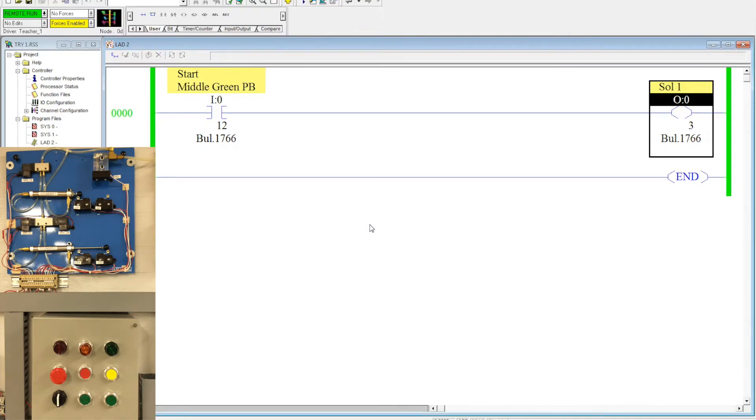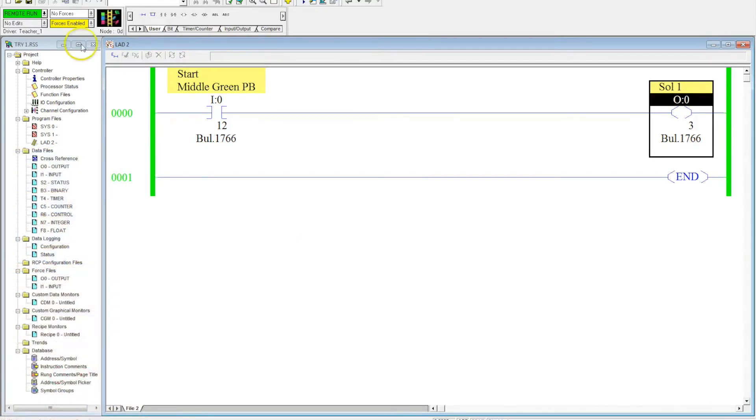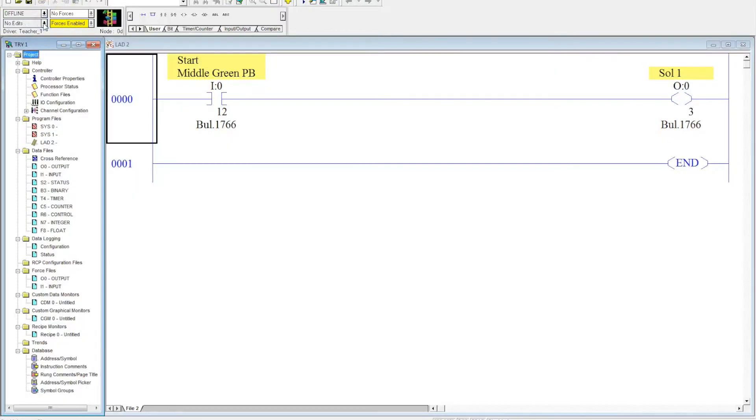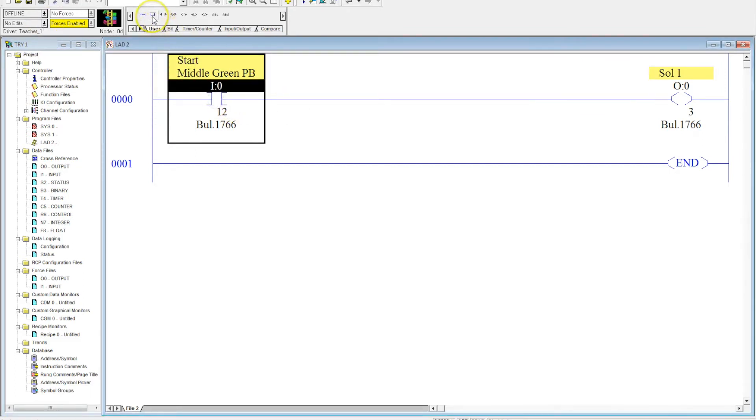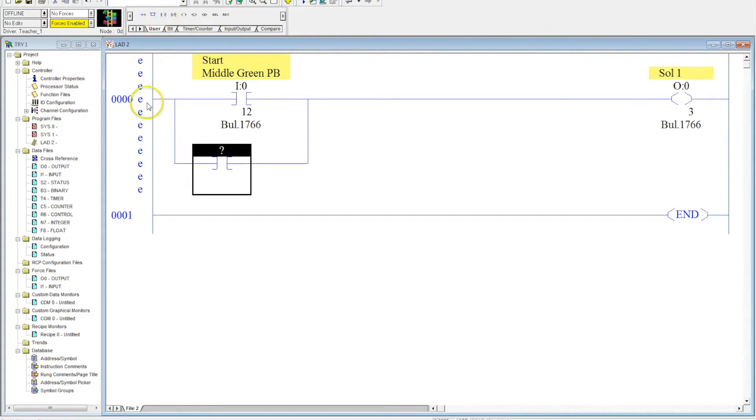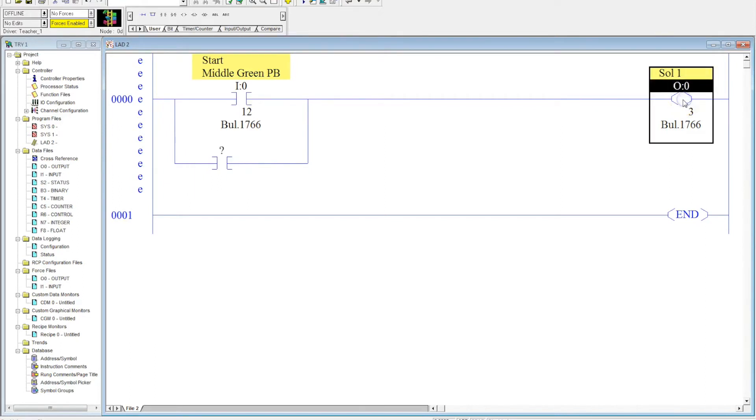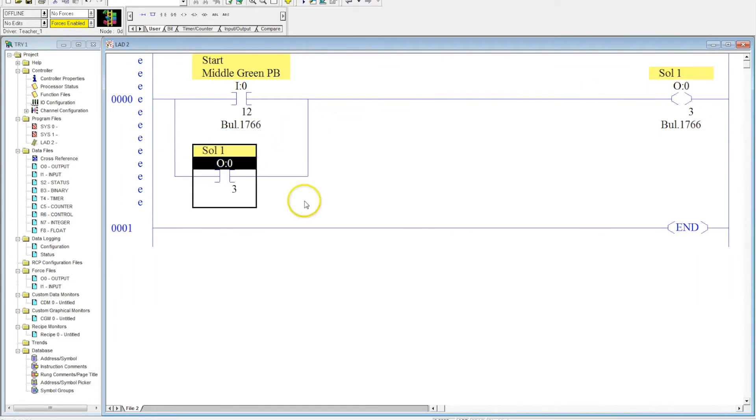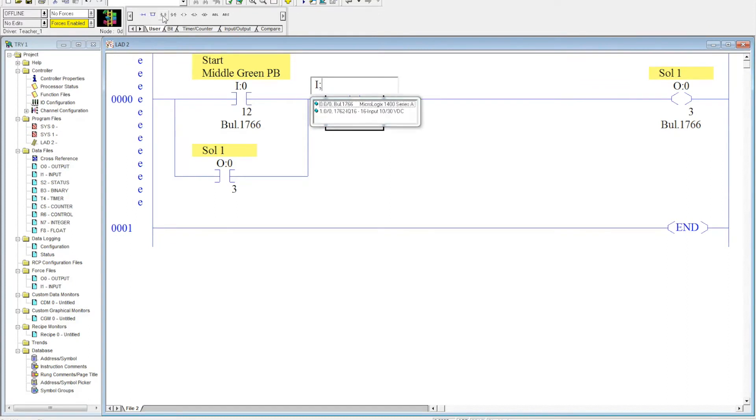So now, let's go ahead and take a look at how we would program this using memory. So now we're going to take this offline so we can put memory around it. This will avoid us needing to pay someone to just sit there and hold the start button. So I come up here. I'm going to select my rung branch. Drag it over just like we did in the parallel video. Select this little corner here. So when I push this button, when I push this icon for the examine if closed instruction, it pops up right where I want it to. Now this is the memory for this output. So what I need to do is select it, grab the black portion, the actual instruction address, drag it down, drop it here. Now this is now memory for that, just like we did with the last basic, very simple memory circuit. Come over here. I'm going to use the stop button again. And that's input colon 0 forward slash 8. Hit enter. I'm going to do a name, so I'm going to call this stop middle red. Hit OK.